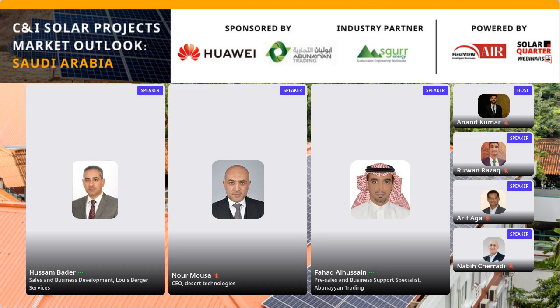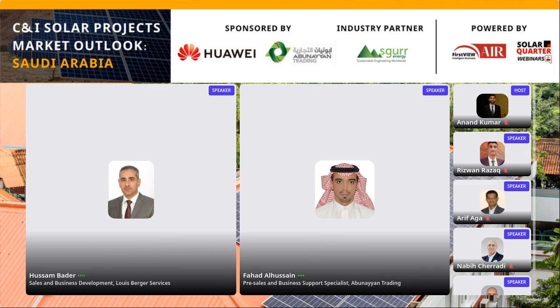Yes, as Mr. Noor and Arif said, for the selection criteria, in order to select the right inverter for your project, you need to consider three main points here in the solar market in Saudi. I would focus on the operating temperature for the inverter, and the efficiency and the power rating of the inverter. This is what I would focus on, because if you want to install an inverter outdoors, it would be a very harsh environment, so you need a reliable inverter to operate in your project.